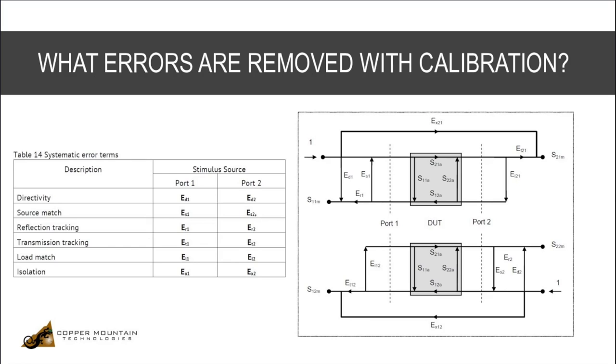if you're looking to the VNA specification, you're probably looking in the wrong place, because I would say that any measurement I make right now with this VNA, most of my phase error is going to be due to these cables. These are really good cables, but move them a little bit and you're going to get phase variation. You need to spend a lot of money to get really phase stable cables. And at that point, then your next step is, what's going on in the VNA?